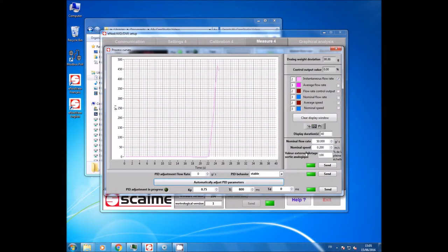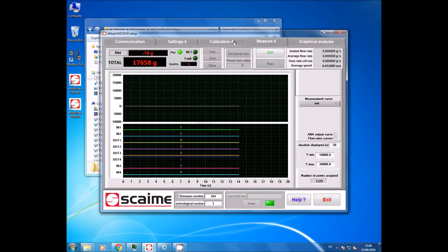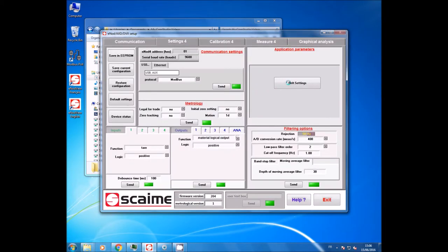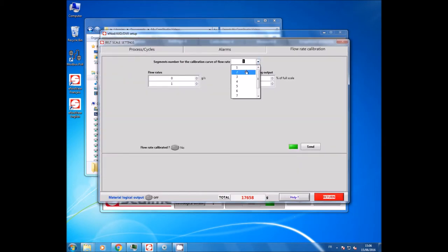Wait for stabilization and note the associated flow rate. Repeat the procedure at several points according to the linearity of your process. Go back to setup, then click on flow rate calibration and enter the values you have found.